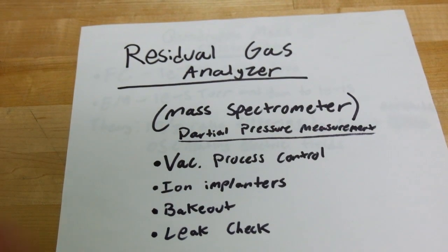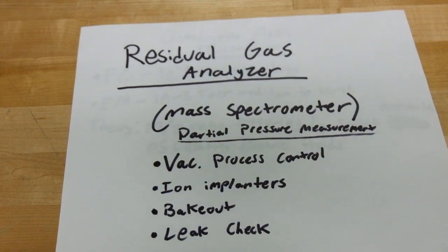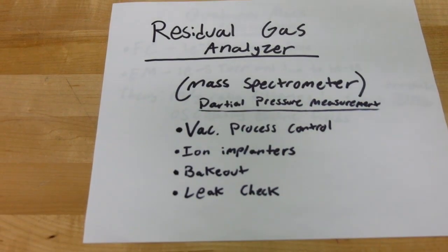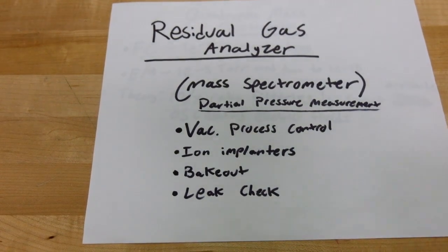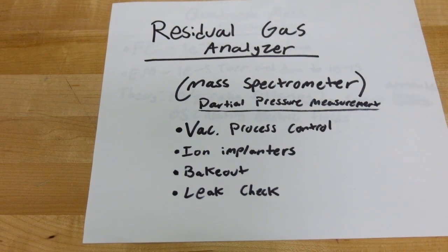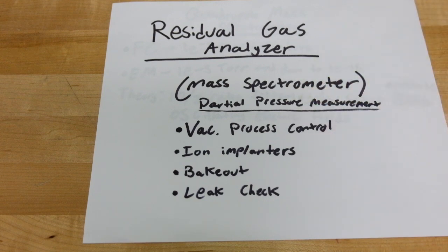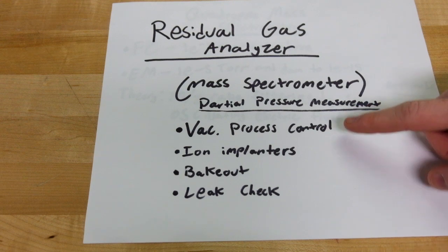In case you're not familiar with RGAs, a residual gas analyzer is basically a tiny mass spectrometer that you'll see on vacuum chambers. Most instruments, like vacuum gauges of different types, measure the total pressure in the chamber, but this is special because it allows you to see partial pressures. It'll print out on the computer a graph of all the different gases and species you have in the chamber and the partial pressure of each of those.